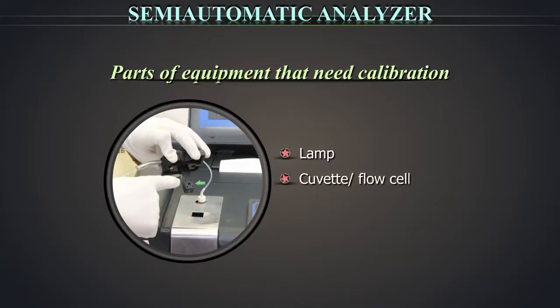The cuvette or the flow cell will get dirty and will need to be cleaned or replaced. The filters also have a specified life and also require change.